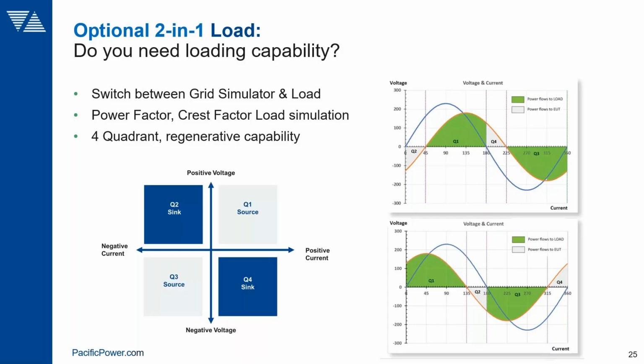So it doubles not just as a source, but also as an electronic load. And being 4-quadrant, it gives you full control over power factor. Phase angle between volts and current can be programmed and controlled, so you can simulate low power factor or high power factor load conditions on your product under test. This is a fairly powerful feature that you can add to some grid simulators if you want to do both.